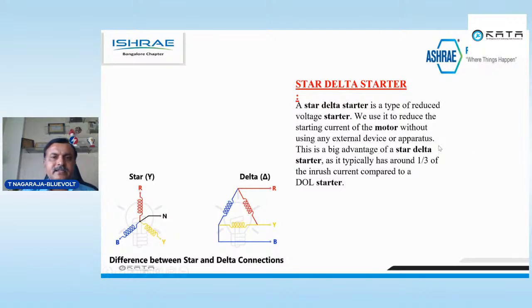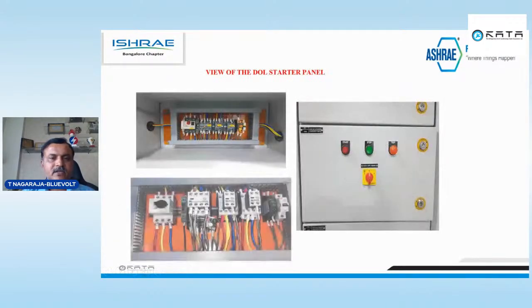A star delta starter is a type of reduced voltage starter. We use it to reduce the starting current of the motor without using any external device or apparatus. This is a big advantage of a star delta starter. This is one star delta starter, how it will look. See, we have 3 contactors, star, delta and main, and one MPCB. This is a different type of MPCB that has been used. Then the timer, the star delta timer, then the control MCB.